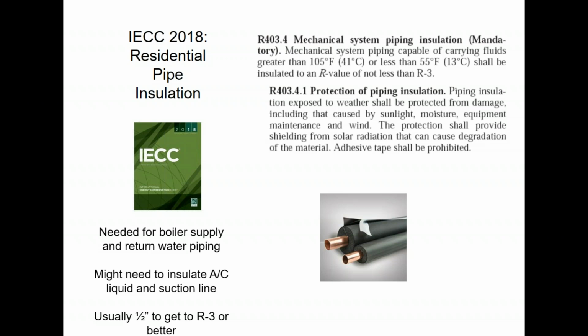Brian asks, are line set manufacturers going to start selling line sets with insulation? They already do sell that. That is a widely available thing from the manufacturers. I don't know if each distributor, including my own distributor, stocks that with regularity. But I know we definitely do that because for a lot of the ductless mini split systems, we already have to insulate both line sets as a requirement for those. Because on a heat pump, you normally want to insulate both anyway, even unrelated to code, because of the temperatures on the heat pump for the opposite modes, it helps preserve some of that heat.